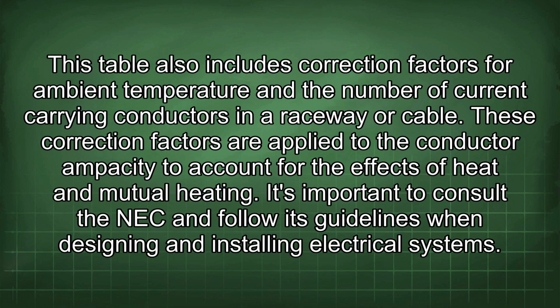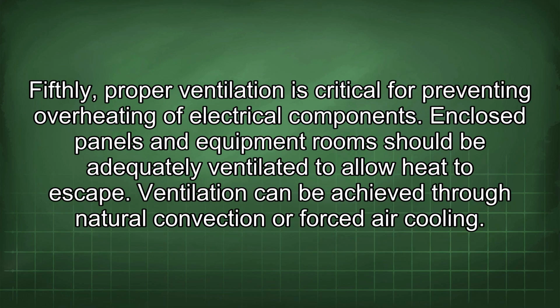These correction factors are applied to the conductor ampacity to account for the effects of heat and mutual heating. It's important to consult the NEC and follow its guidelines when designing and installing electrical systems. Fifthly, proper ventilation is critical for preventing overheating of electrical components. Enclosed panels and equipment rooms should be adequately ventilated to allow heat to escape. Ventilation can be achieved through natural convection or forced air cooling.